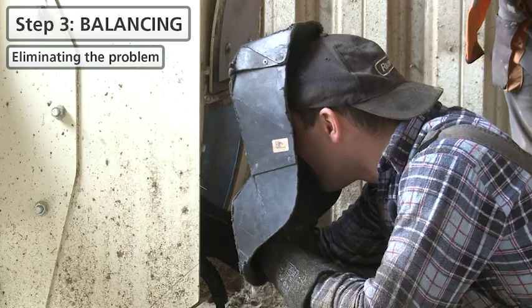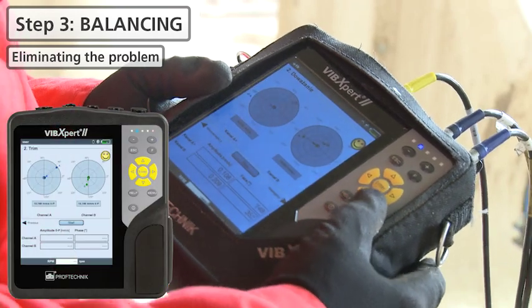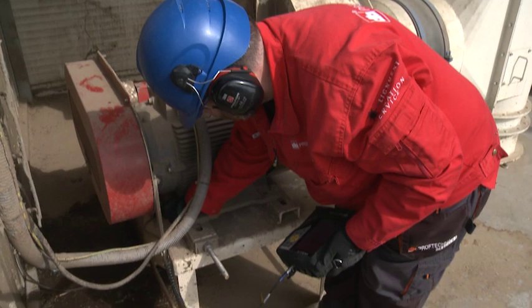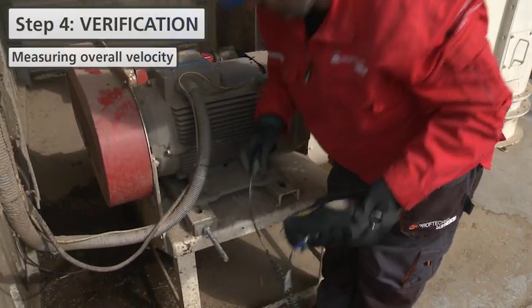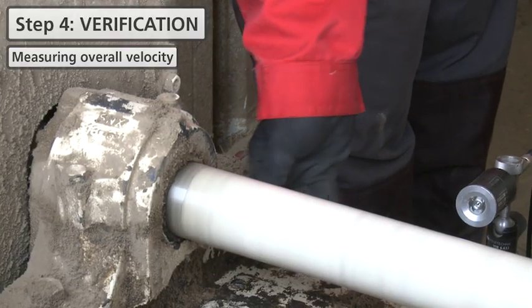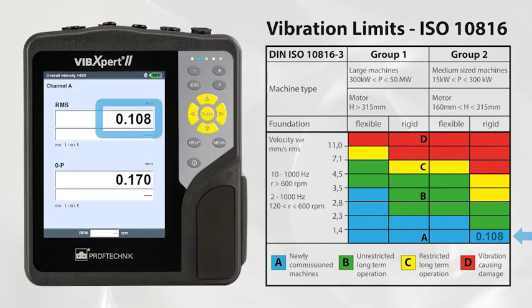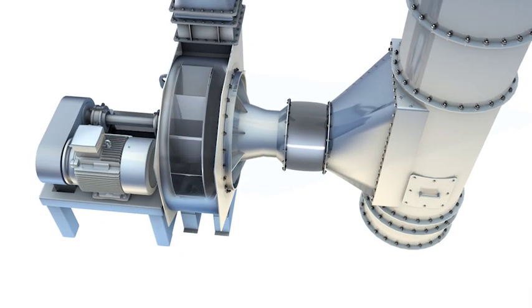The correction weight is welded to the fan. Tom then measures the overall vibration level again. Now let us check the final results. As we can see, thanks to the VIBXpert II vibration analyzer, the root cause of excess vibration was diagnosed and eliminated.